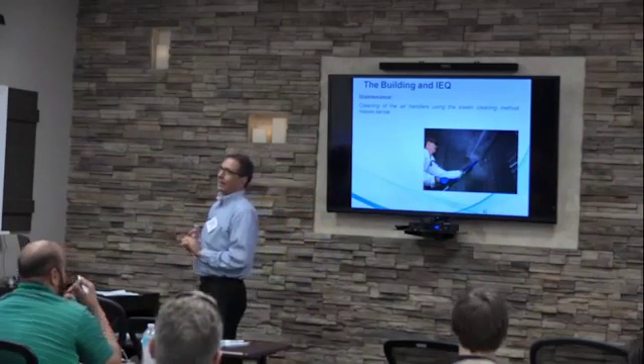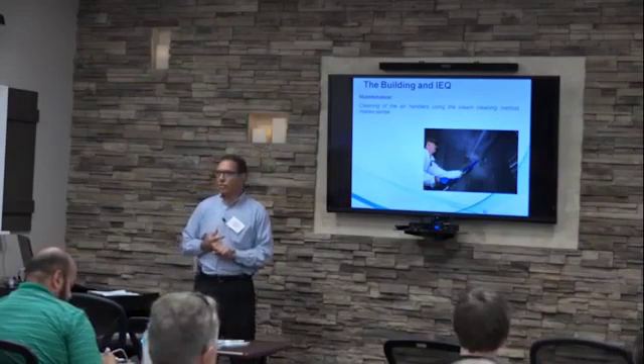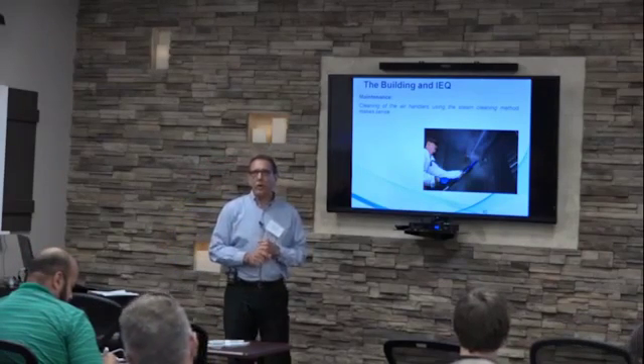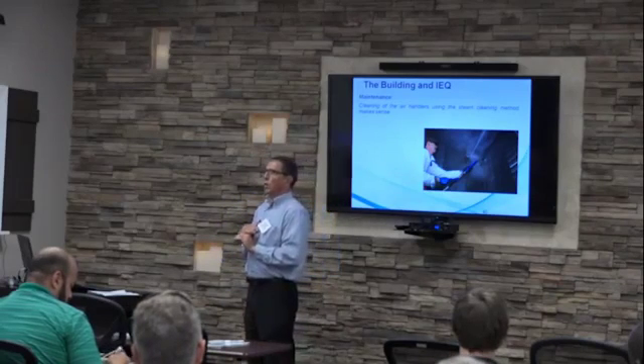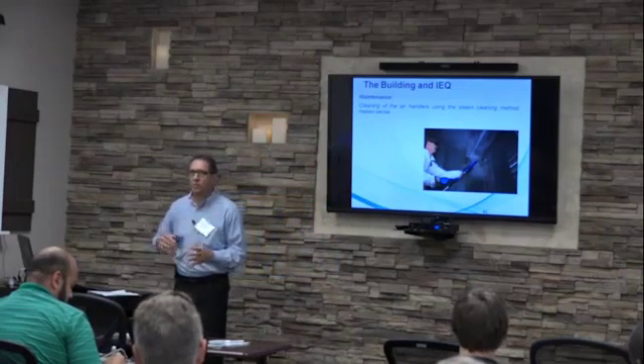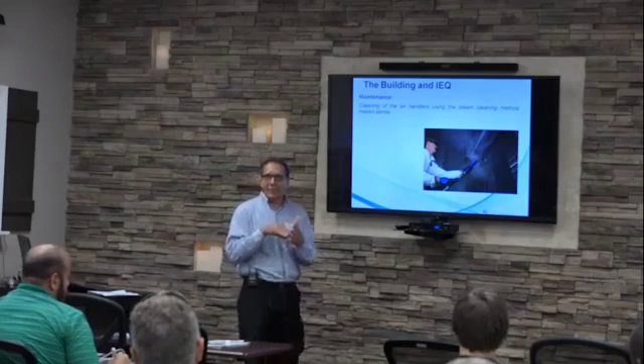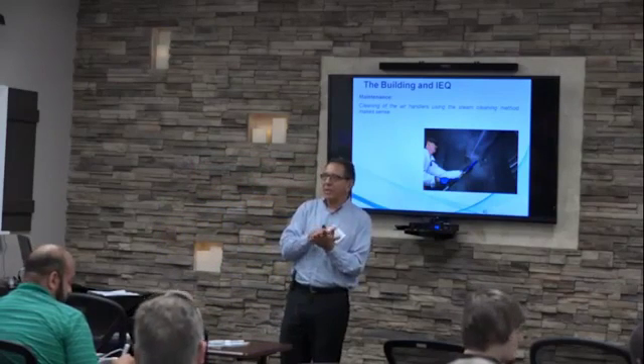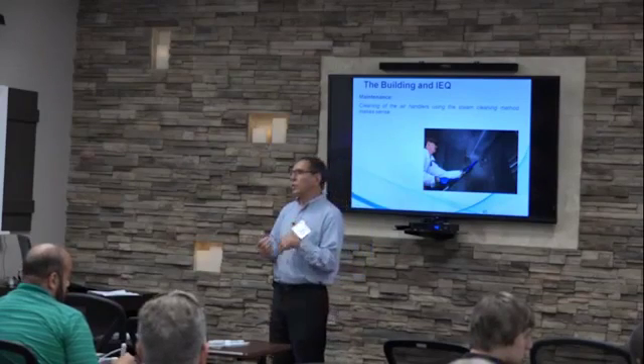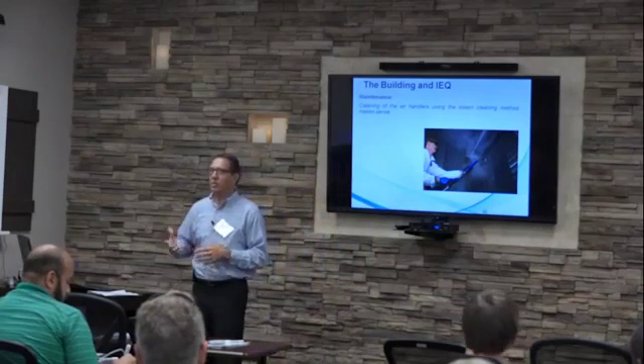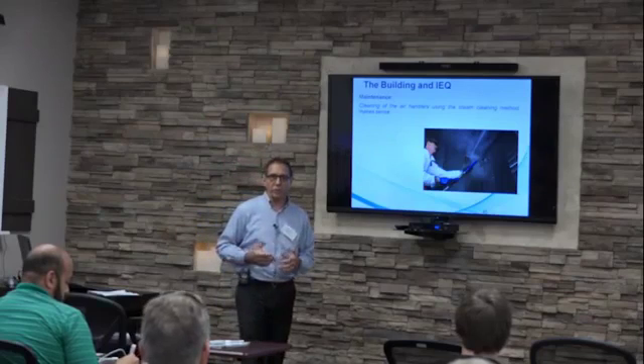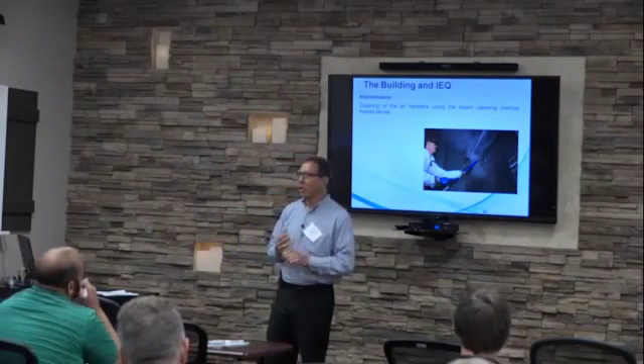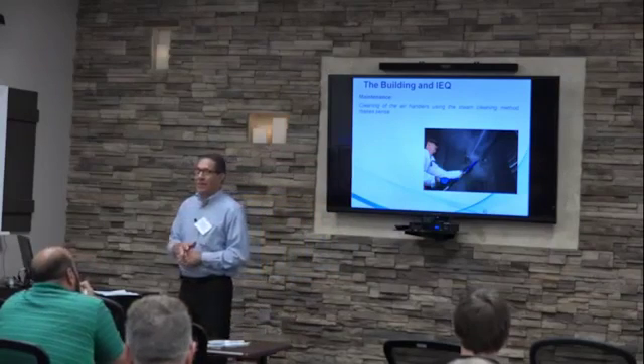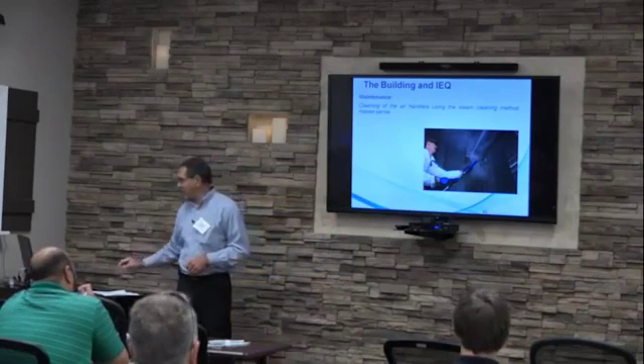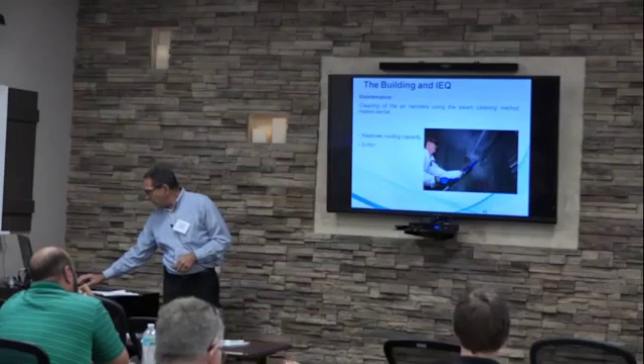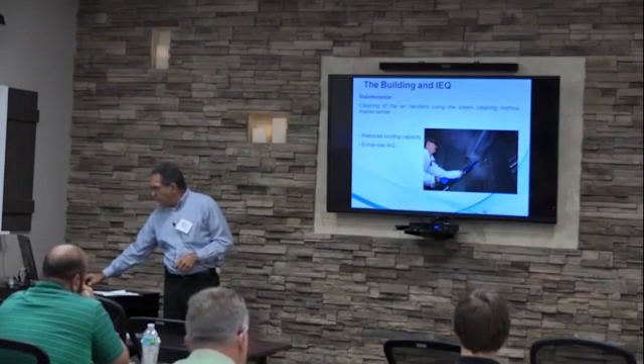Going into maintenance, again, cooling coils and air conditioning systems are a very important area that we need to give attention. If we clean cooling coils, hopefully nobody is using pressure washers anymore, because pressure washers are forcing this dust and things further deep into the coils. Steam cleaning is a much more efficient way of cleaning coils. It's going to sanitize, kill the bacteria and fungi, and it's going to remove the vast majority of the contaminants that you have inside of the pack.